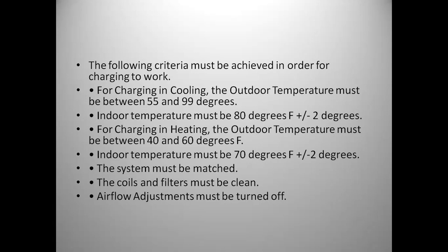When you're using an inverter system, it must be matched up to an AHRI matched coil that also has an EEV within the coil or the air handler. If not, it will work fine in cooling for the most part. Or I take that back. It'll work okay in heating, but when it goes into cooling, it's going to run quite low. So you must have the proper matched system, and that is a proper matched air handler, the RHMV air handler, or, if you're doing a dual fuel gas furnace, you have to have a proper coil that has an EEV.